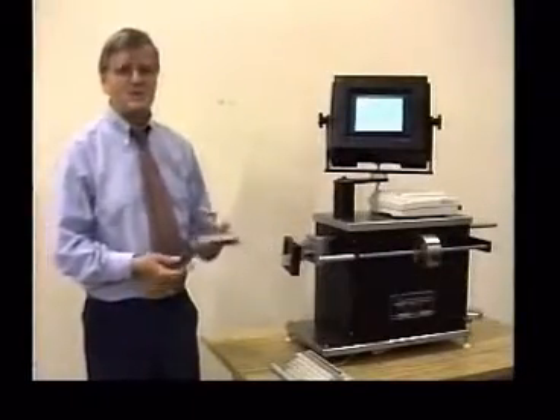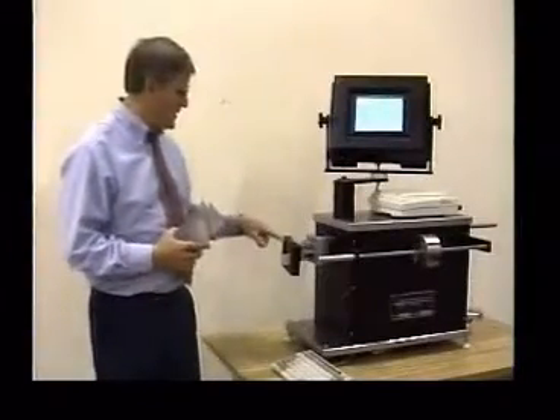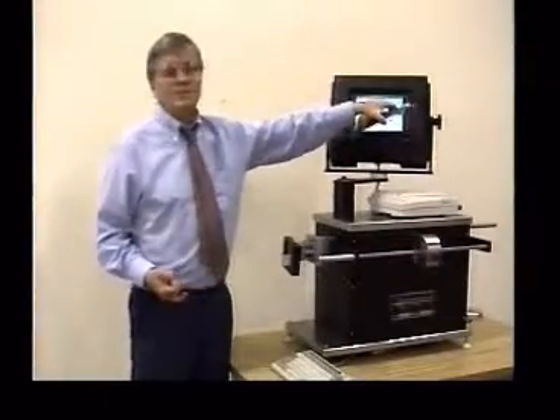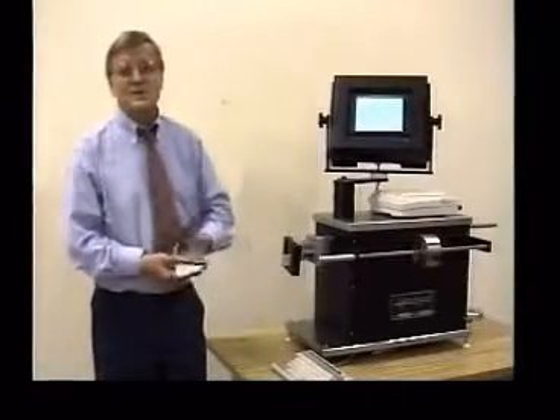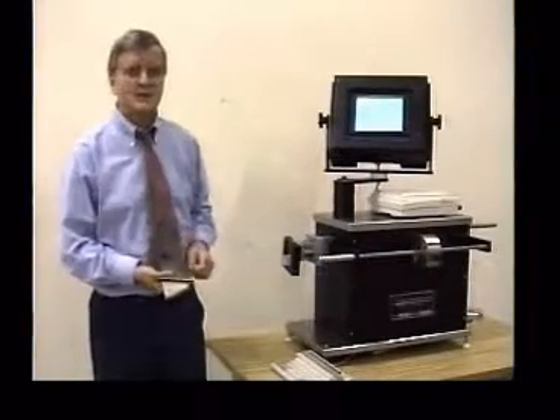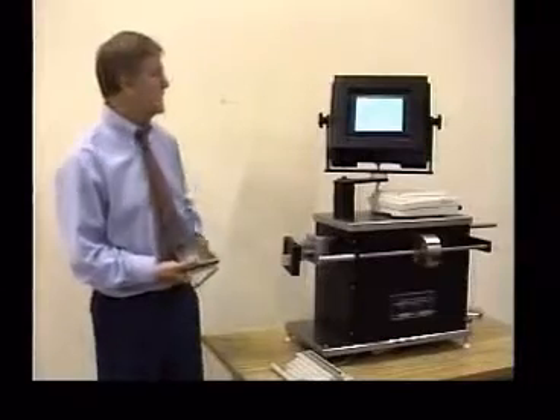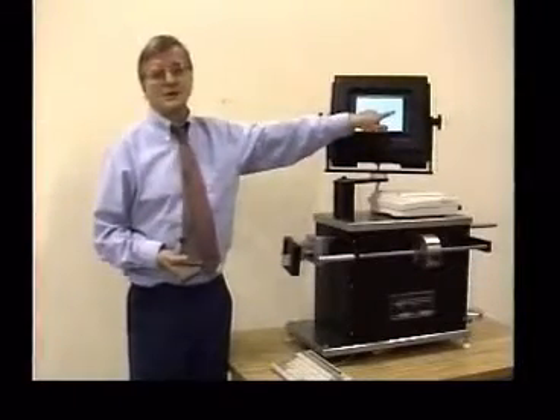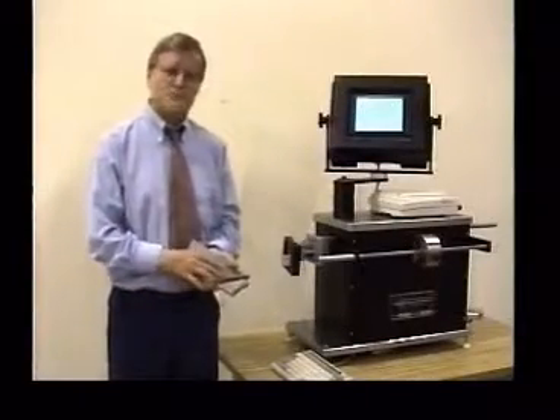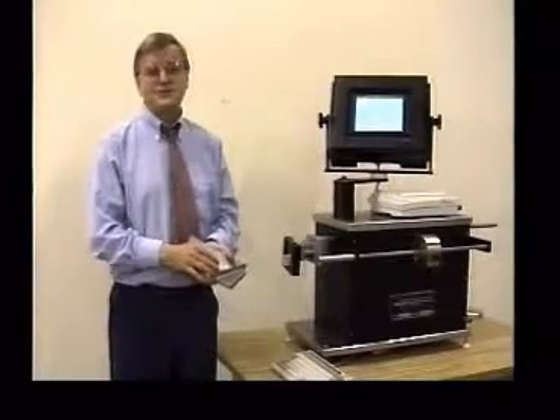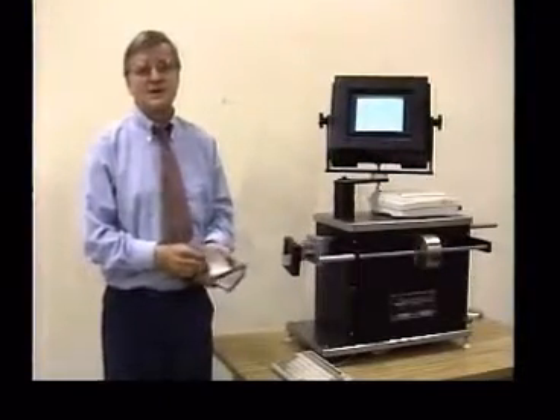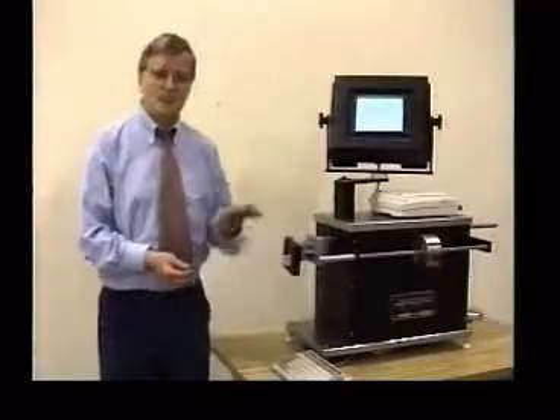This is a Space Electronics model MW900 moment weight machine. We've got it set up with an adapter that fits a dovetail blade. The display here indicates the moment in ounce inches. If you've been using a moment weight machine in the past, you may notice something about this machine which is unusual, and that is that the display indicates the moment to the nearest hundredth of an ounce inch rather than the nearest tenth of an ounce inch. And the reason we do this is because of the incredible accuracy of this machine. Expressed in terms of full-scale moment, this machine has an accuracy that is typically about 2 parts per million.